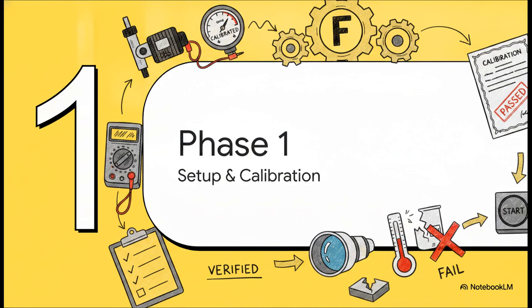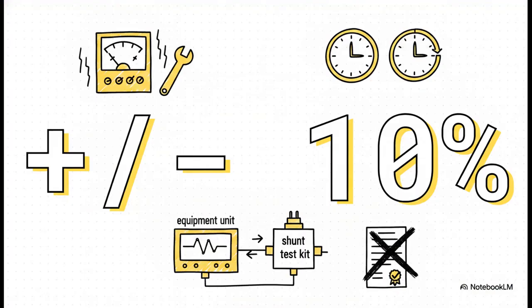Starting with Phase 1, setup and calibration checks. Look, if you don't verify your equipment, you've essentially failed the test before you've even inspected a single part. Calibration isn't just paperwork. It's literally the foundation of a valid test. The standard mandates that the current indicated on your stationary unit's display is no more than plus or minus 10% of the true current value. And hey, if you're using multi-directional equipment, that tolerance drops to a super tight plus or minus 5%.